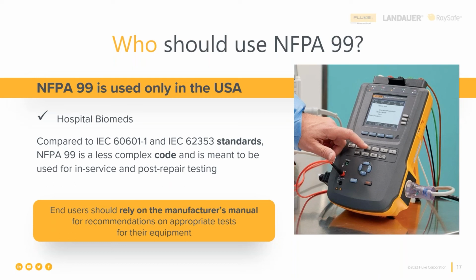A lot of times in the United States, the reason we're going to NFPA 99 is because we believe that it is less of a burden on our limited biomedical engineer and technician staffs in most hospitals. And indeed, it is less burdensome, but it only requires measurements on incoming inspection, both kinds of incoming inspection, by the way, when product is new and when it's come back from repair, and then after any repair we do in-house. Otherwise, it's just a visual inspection, which may not be sufficient even on an annual basis. We need the measurements in order to verify with objective, independent evidence that the medical device, from an electrical safety point of view, is safe and effective for clinical use.